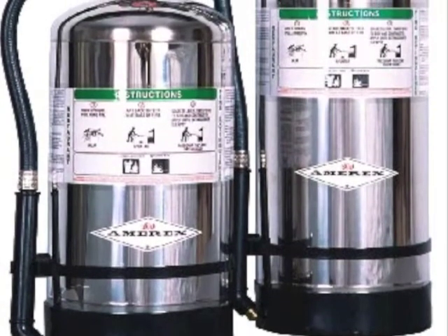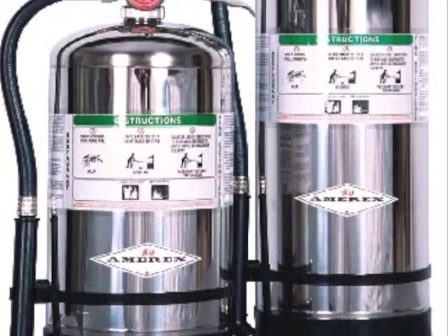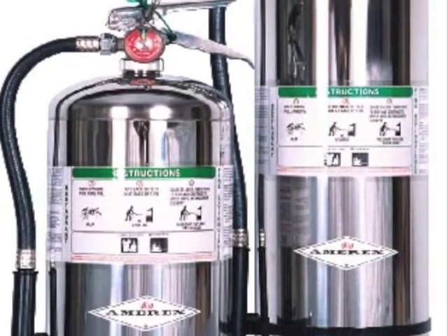Dry chemical fire extinguishers extinguish the fire primarily by interrupting the chemical reaction of the fire triangle. Today's most widely used type of fire extinguisher is the multi-purpose dry chemical that is effective on Class A, B, and C fires. This agent also works by creating a barrier between the oxygen element and the fuel element on a Class A fire. Wet chemical is a new agent that extinguishes the fire by removing the heat of the fire triangle and preventing reignition by creating a barrier between the oxygen and fuel element.